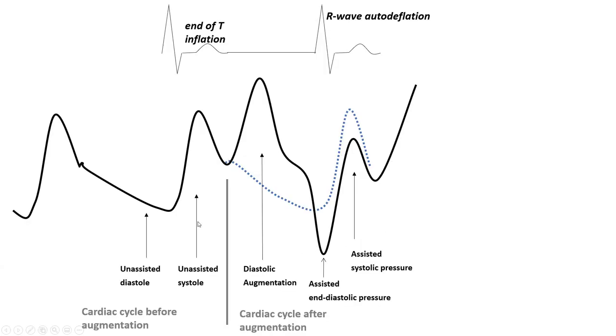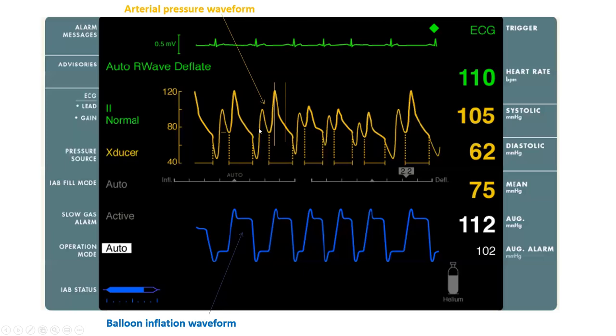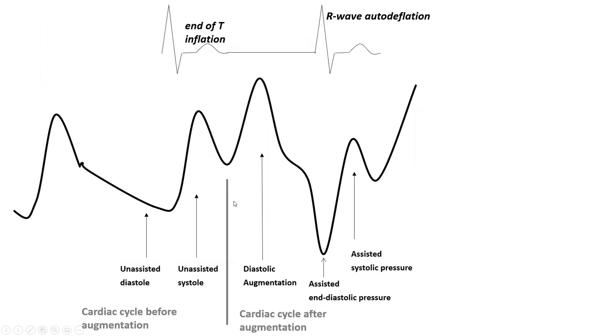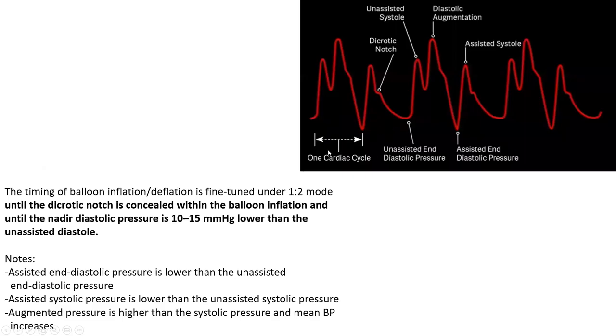Now, how do you do that adjustment? Once you're augmenting one-to-one, it's hard to tell whether you're augmenting properly, whether your diastolic and systolic pressures have declined compared to before augmentation. So the way to compare that is to go under 1-to-2 mode, and the machine will make adjustments of those pressures automatically. You often don't need to do that, but it will be clever for you to verify that the augmentation is appropriate and you're having the proper waveform. The way to verify that is to go under 1-to-2 or 1-to-3 mode, typically 1-to-2 mode.